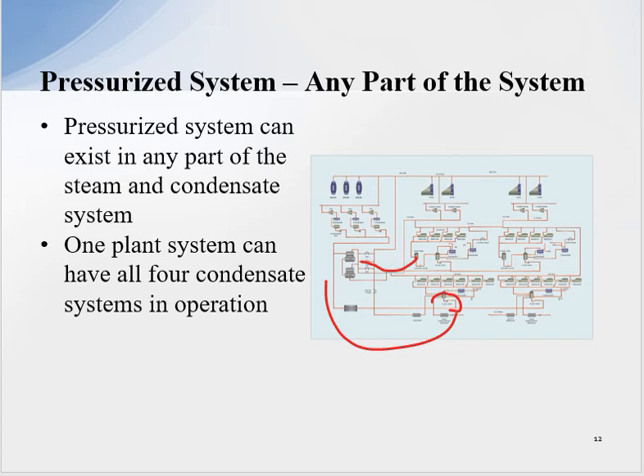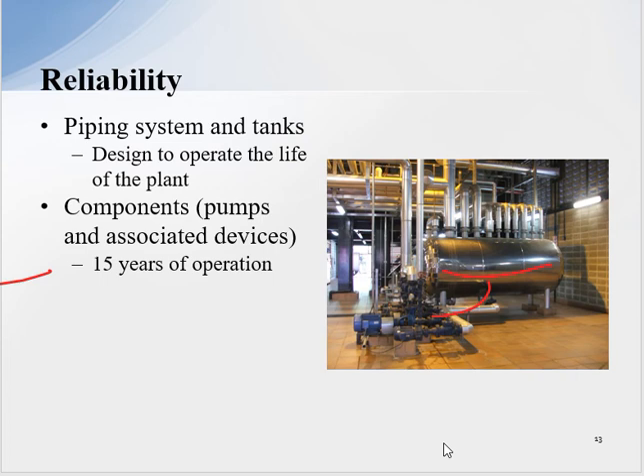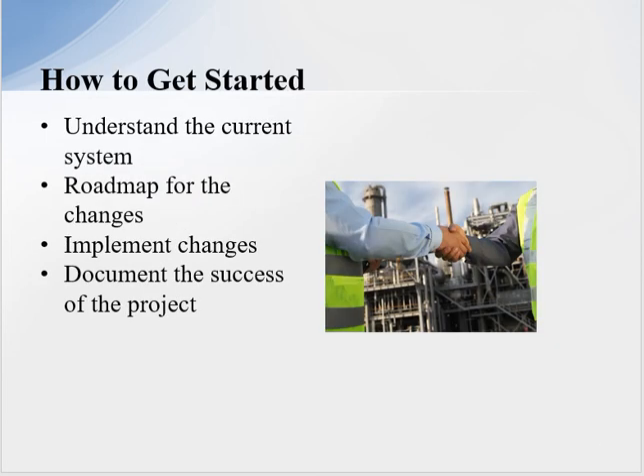With condensate pumps, reliability is essential. That means industrial pumps — which have a cost — but we want an operational life of fifteen years with no pump failures, specifically for condensate. A condensate pump is handling water, which is the simplest thing to pump, so it should last twenty-five years. But that comes down to design: the tank designed correctly and the pumps specified with correct NPSH. In a properly designed system, where a pump is needed, understand it as a system and make sure you truly need a condensate pump before installing one.